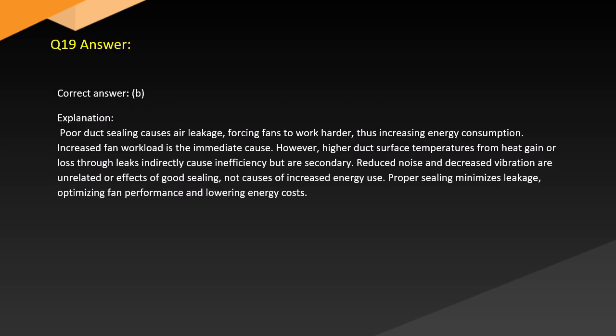Answer. Correct answer, B. Explanation. Poor duct sealing causes air leakage, forcing fans to work harder, thus increasing energy consumption. Increased fan workload is the immediate cause. However, higher duct surface temperatures from heat gain or loss through leaks indirectly cause inefficiency, but as secondary. Reduced noise and decreased vibration are unrelated, or effects of good sealing, not causes of increased energy use. Proper sealing minimizes leaks, optimizing fan performance and lowering energy costs.